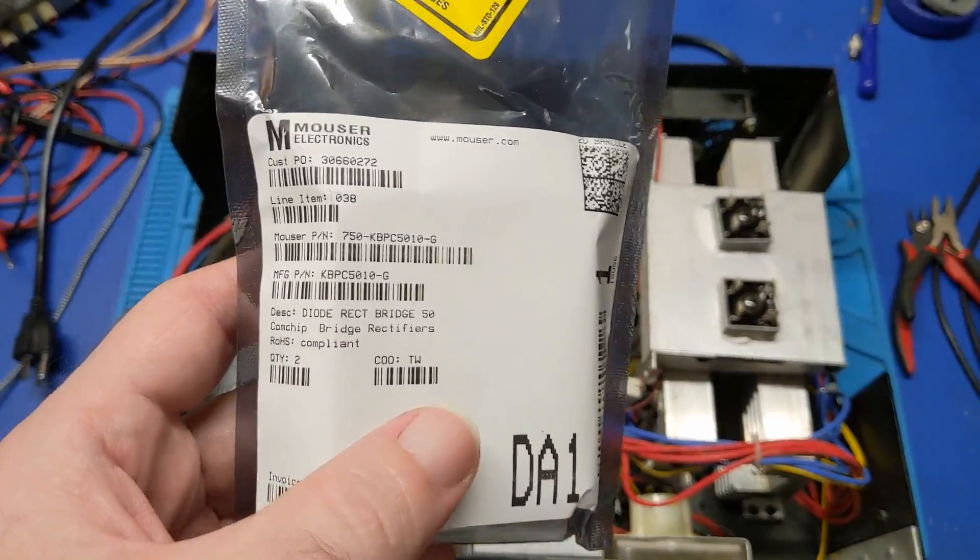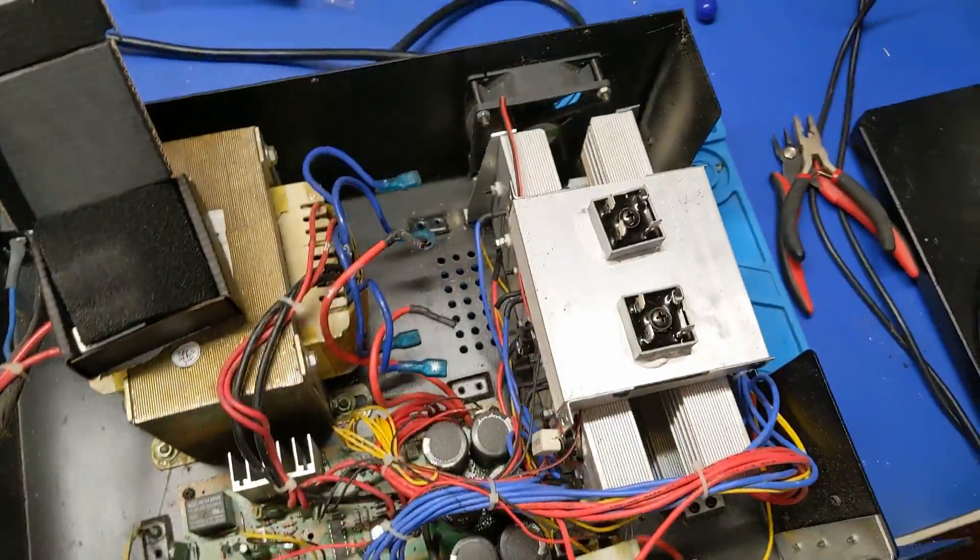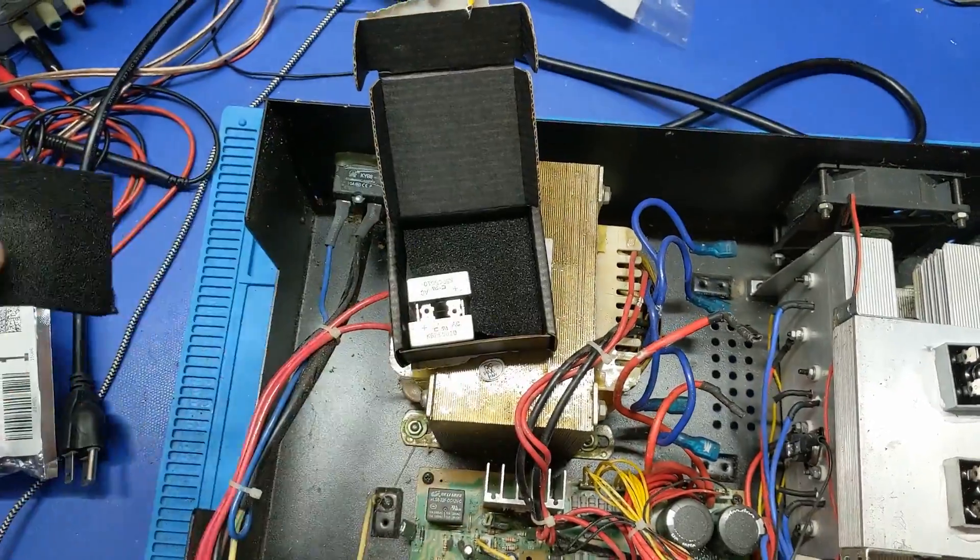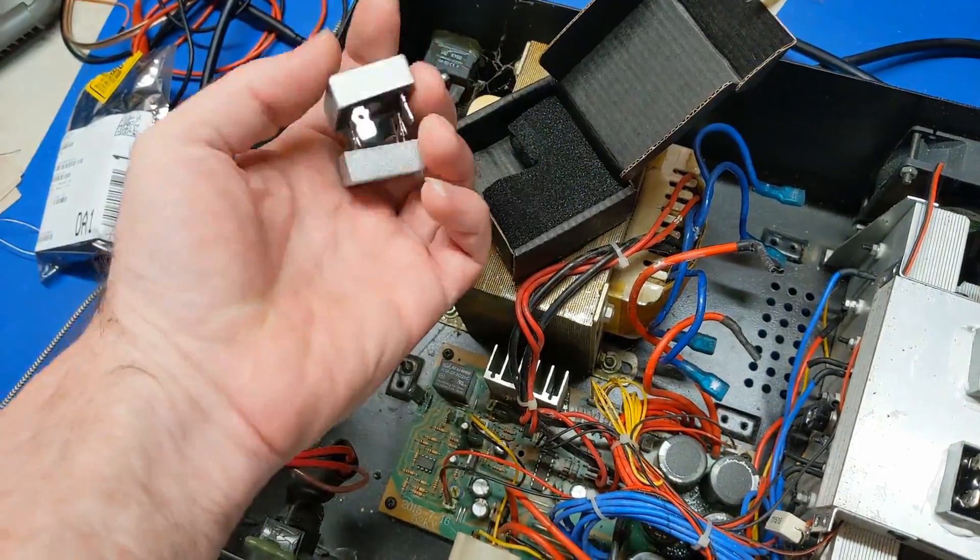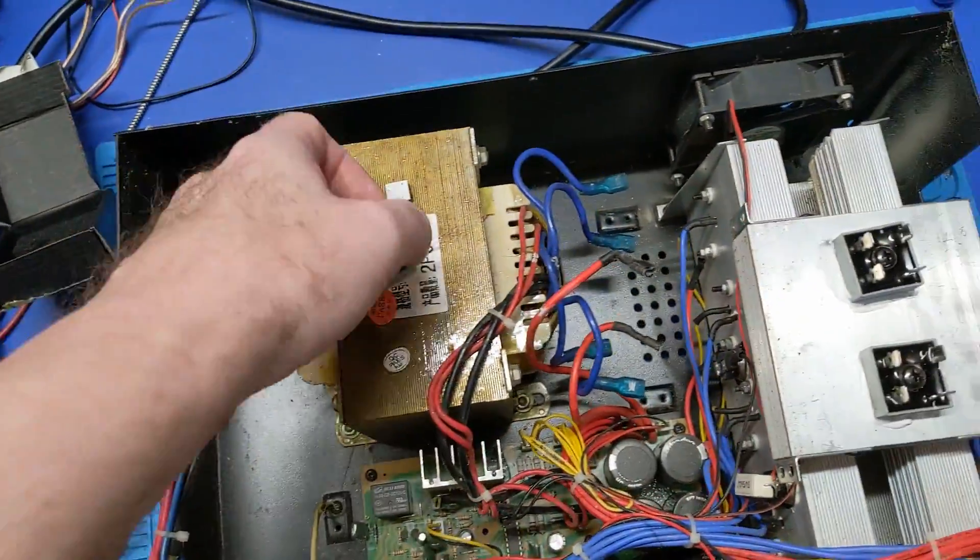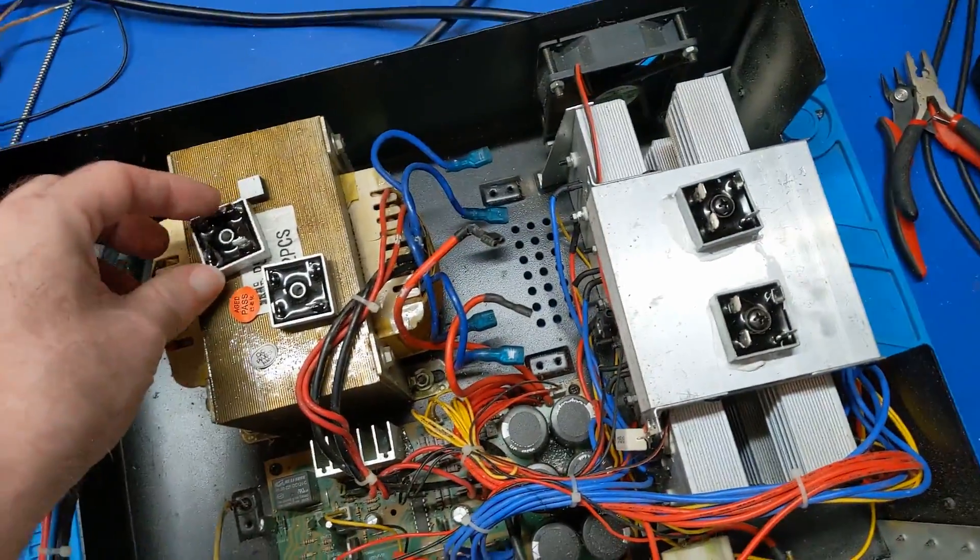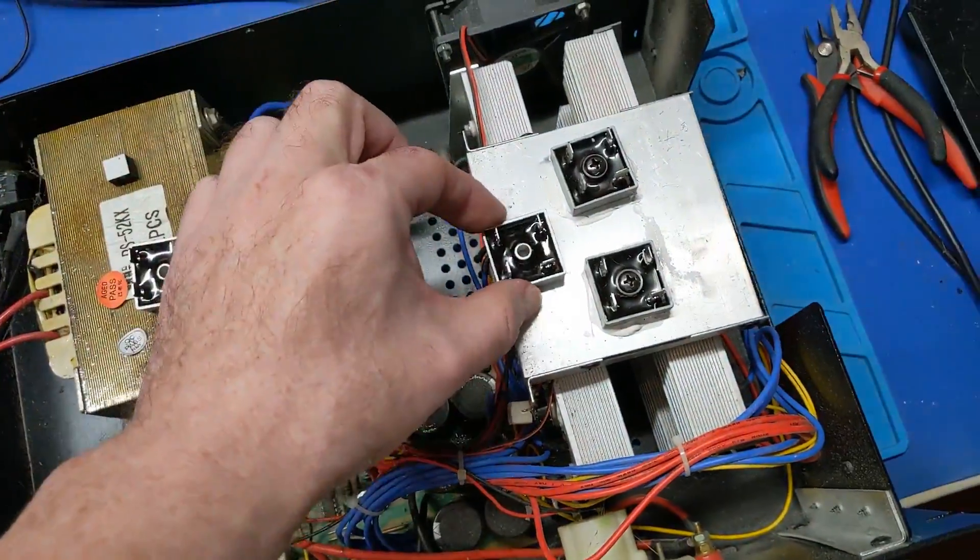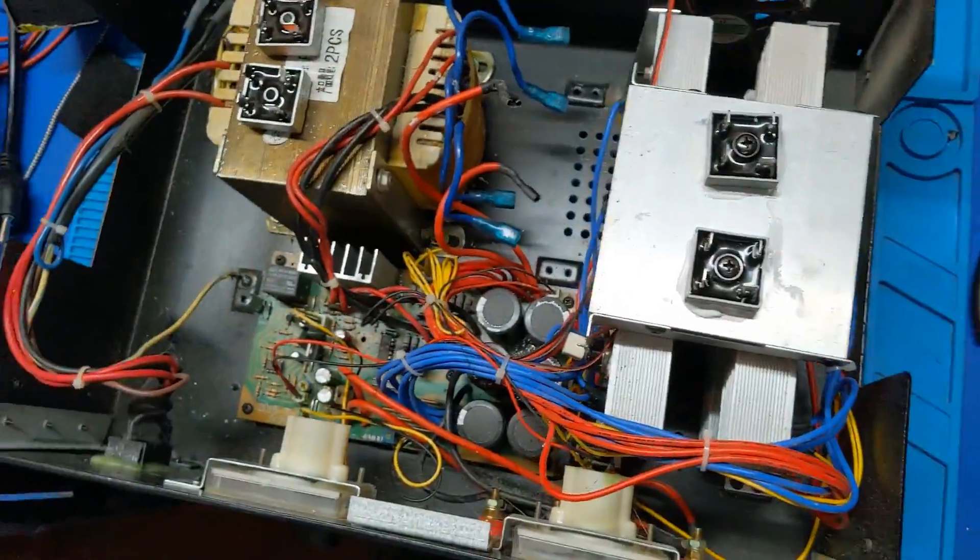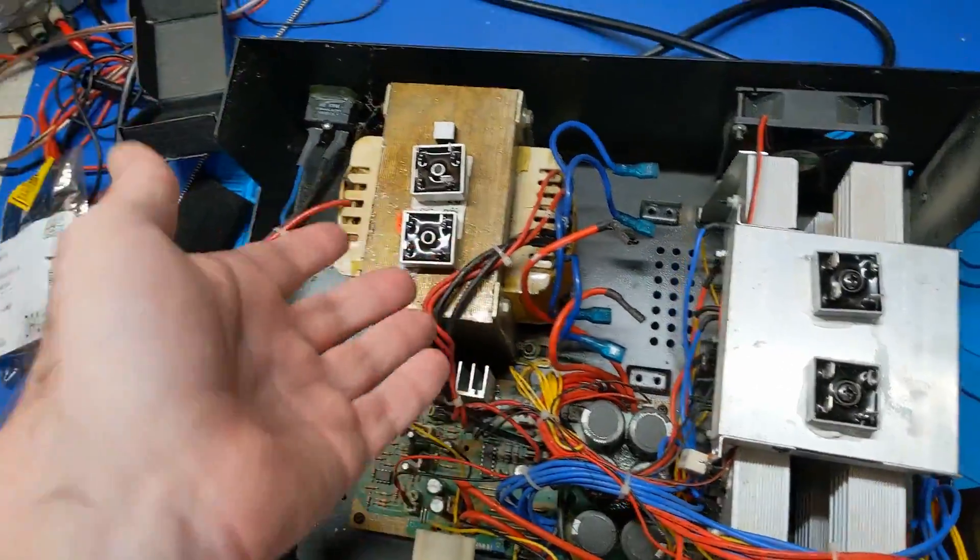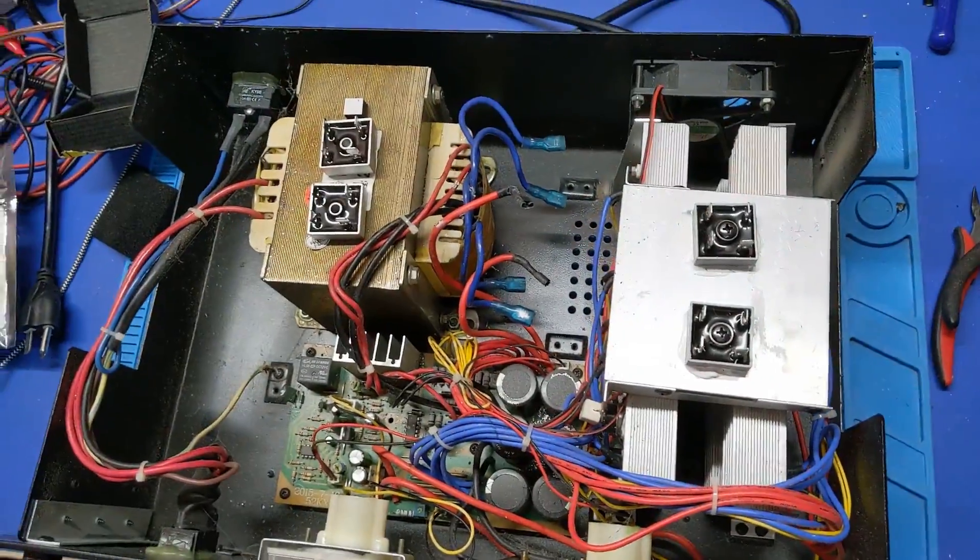Alright, so we've got some brand new rectifiers, KBPC5010, which is what these are. And here we go. I didn't buy just one, I bought a pair of them because I'm going to change both of them out. That's a funky way to package that, but okay. So yes, we have two rectifiers here and they're exactly the same, so they should go in exactly the same way and that should solve our problem. Because this one was shorted. So let's go ahead and change both of them because whatever shorted that one, both of them were subjected to the same surge current. So we're just going to go ahead and change both of them out.